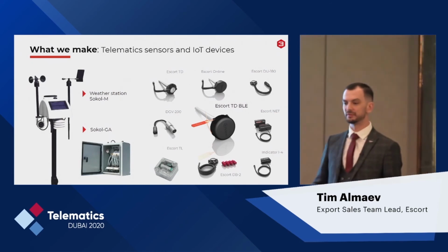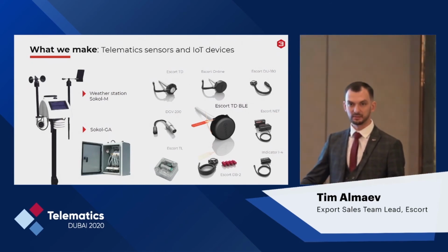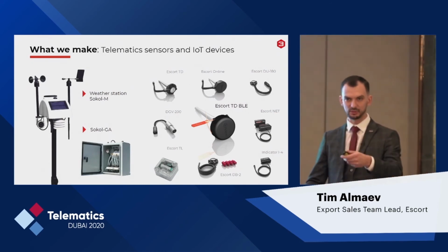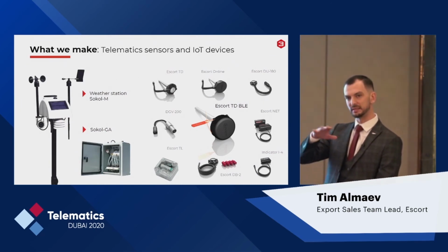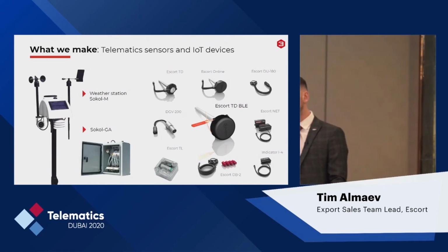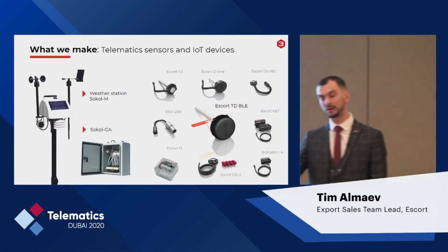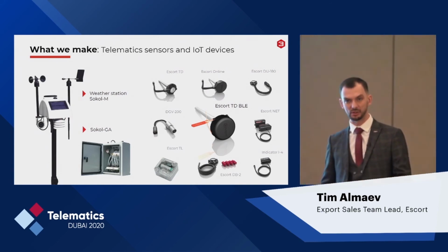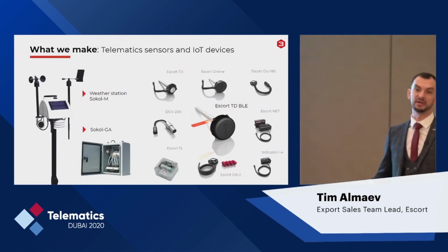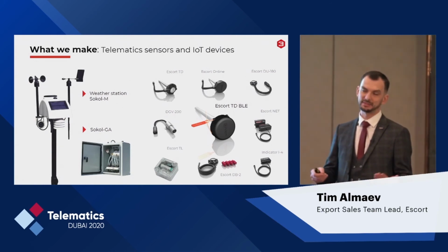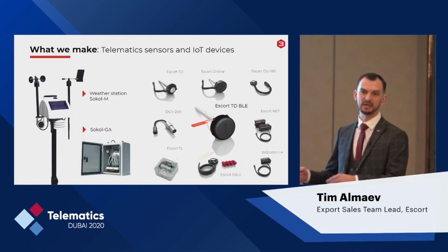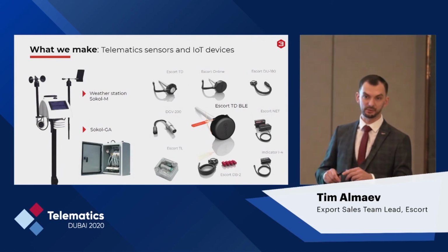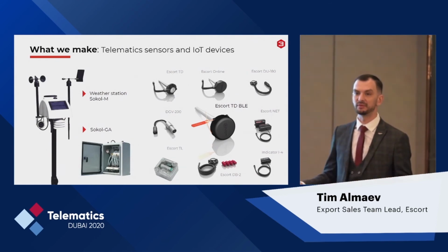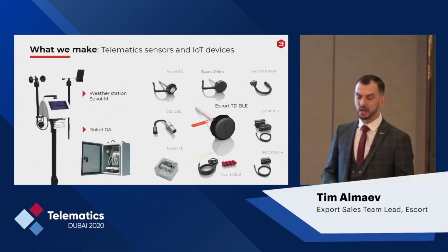So how does it look in real life? You cut the sensor to the size of the tank, because it has to be as long as the tank is deep. Then we hit dry calibration. Now it's calibrated and ready to be installed. So the next step is the tank calibration. Basically, we have to teach the sensor what tank it was installed in by creating a calibration table, which is the same. You have to do the portions of the fillings and such.